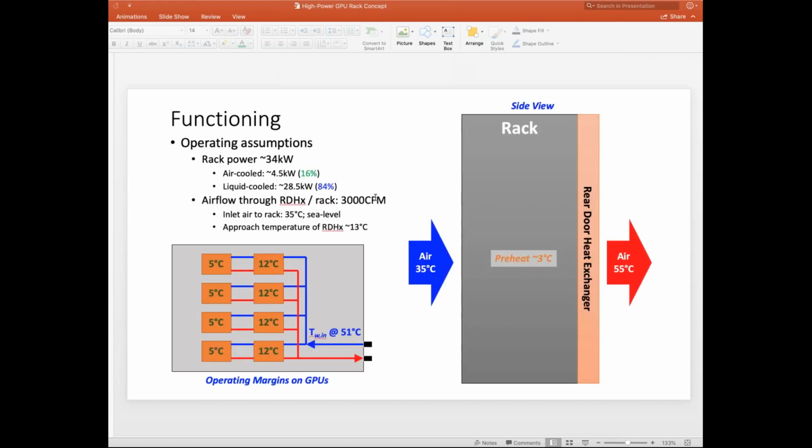I think this is the last slide, on functional. As I said, we are currently thinking that if we fully populate, it's going to be around 34 kilowatts. And I heard that some companies are looking at even higher for the GPU. But mainly we are assuming, based on the 3U GPU boxes, that the worst case rack power dissipation is around 30 to 38 kilowatts.